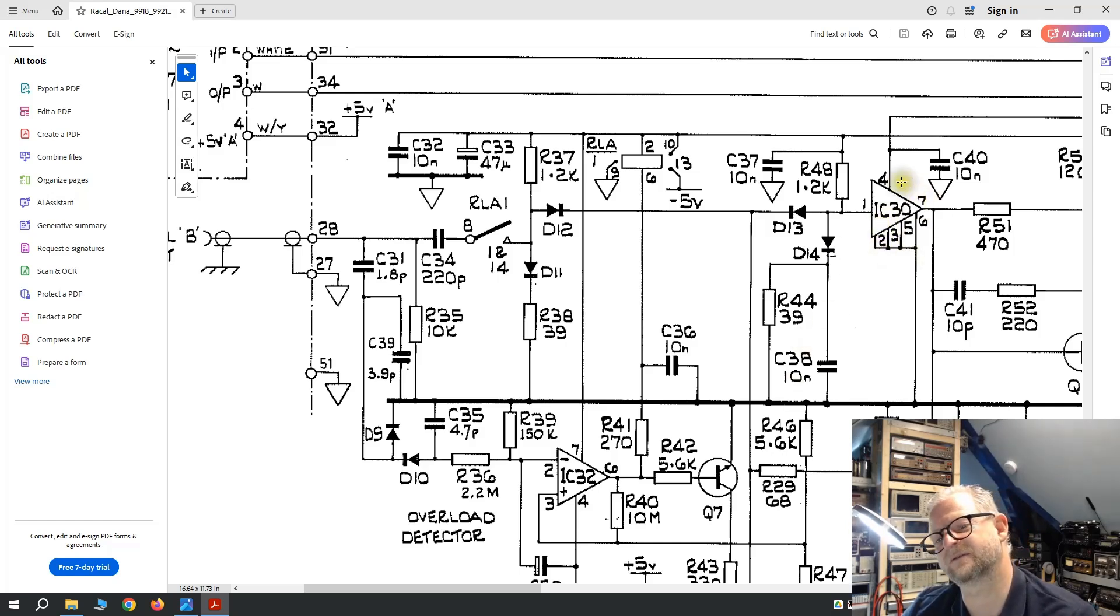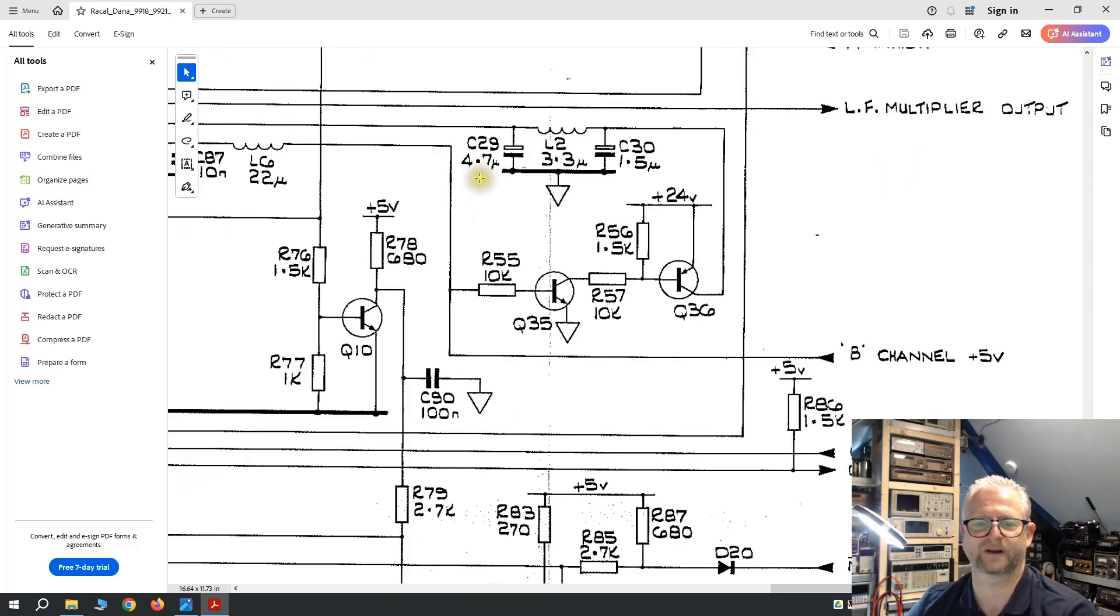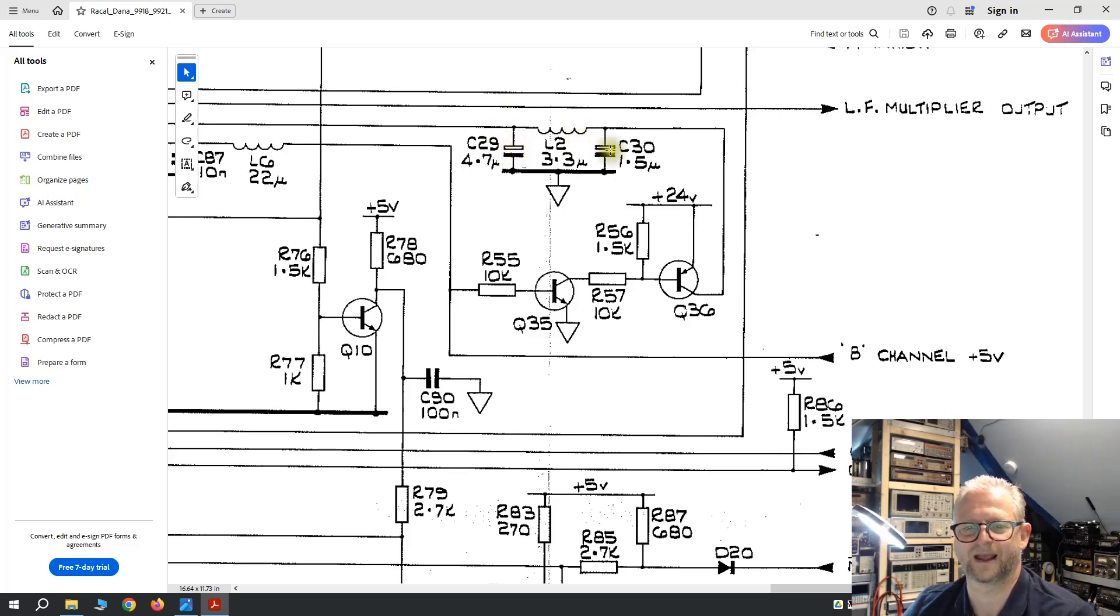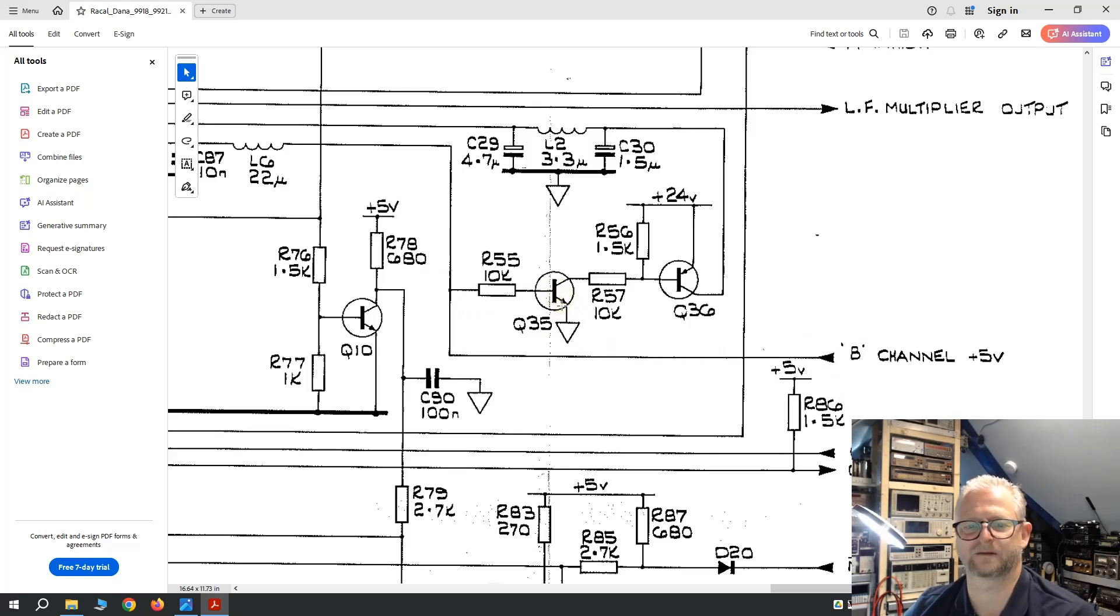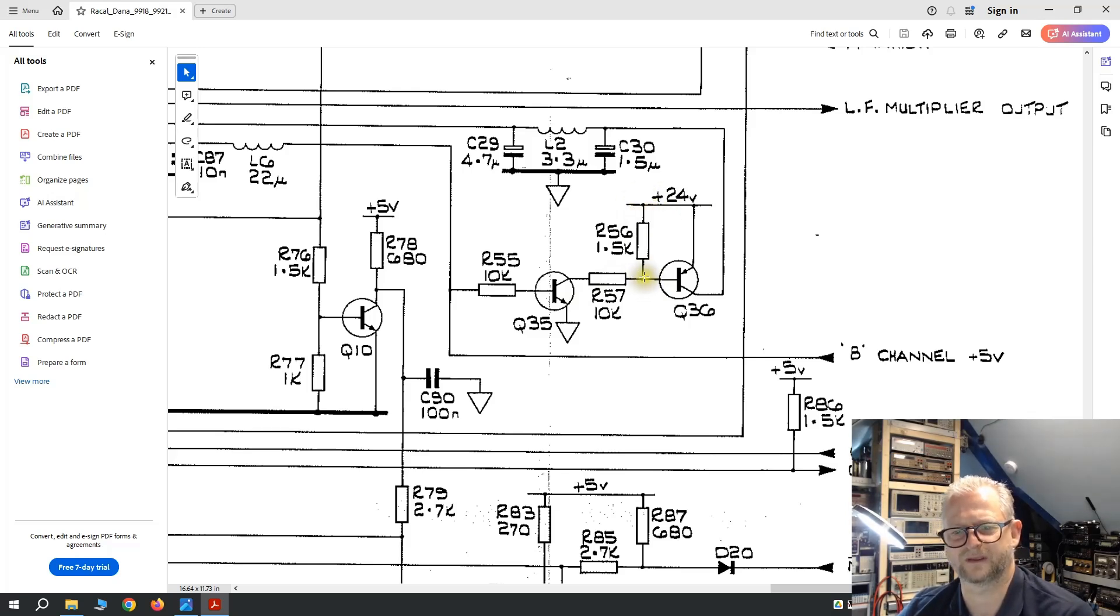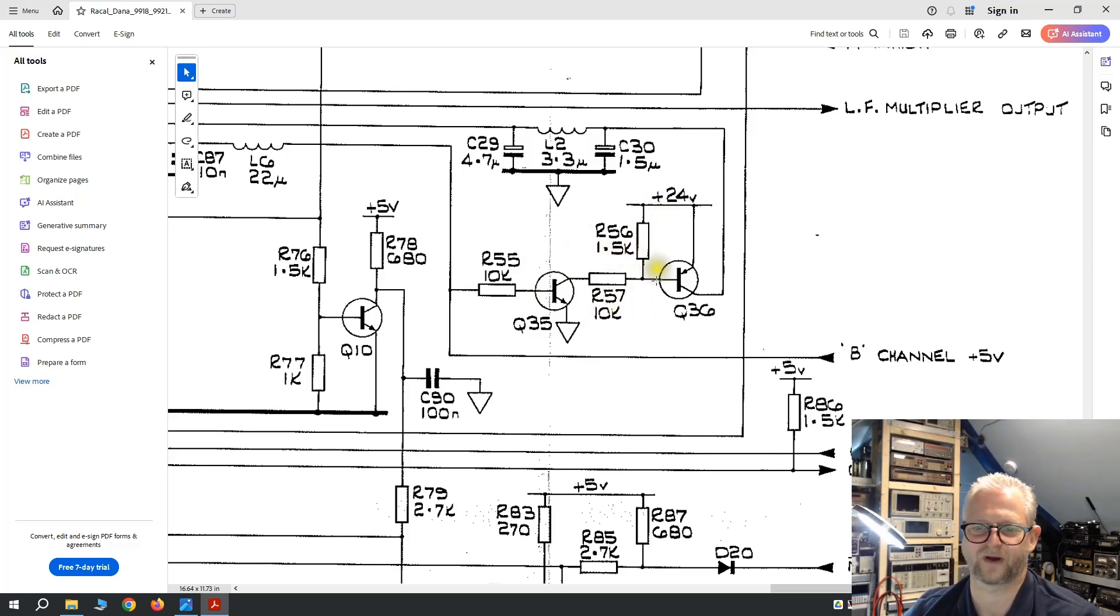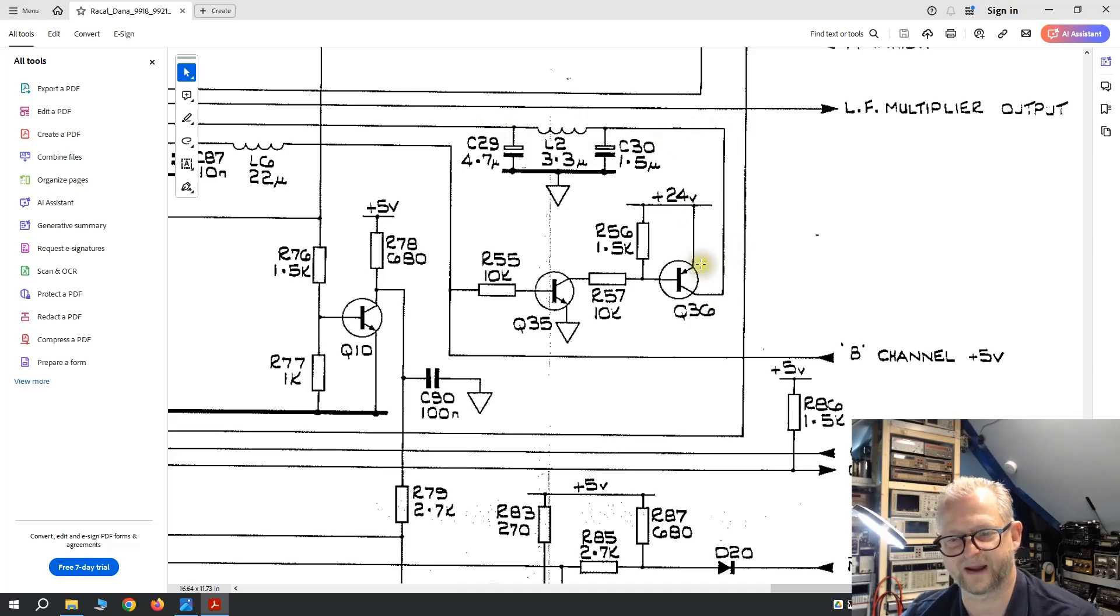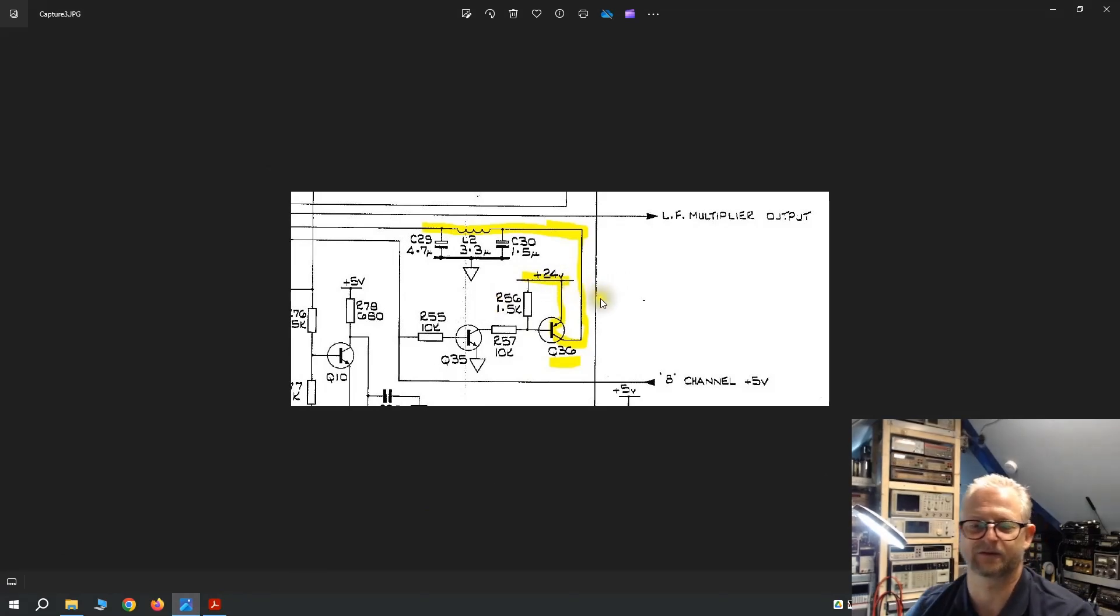When we started to measure the voltage there was no voltage in the first place. So we went further in the circuit and it turned out that one of these tantalum capacitors was shorted. I took that one out and we still didn't have power. This here is connected to the B switch. It switches the B channel and then puts power on the amplifier. The signal here was going from 24 volts to 21 volts. Because if it switches here this pulls it down and we get the voltage divider, dividing this 24 volts over this 10k and 1.5k. So it should have been going open and getting the voltage through to the amplifier, and it didn't do that. So we just shorted these two and then we had a readout on the B channel. I ordered this transistor and we're going to replace that one today, and then clean the whole device.